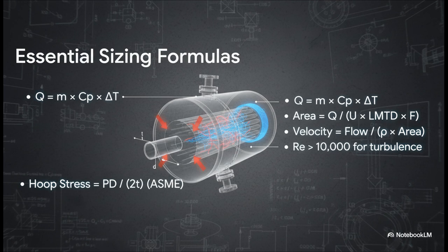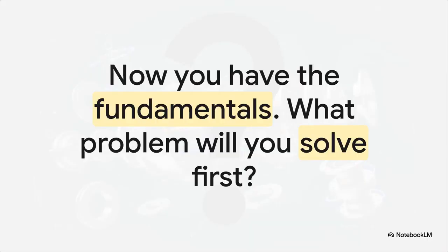And finally, we turn to the ASME pressure vessel code. We use the hoop stress formula, which connects pressure and diameter to material stress, to calculate the absolute minimum wall thickness we need for our shell and tubes to safely handle the pressure. So there you have it. From TEMA types and LMTD calculations all the way to baffle design and material selection, we've walked through the entire design process. You now have the fundamental building blocks to go out and tackle any shell and tube exchanger design challenge.